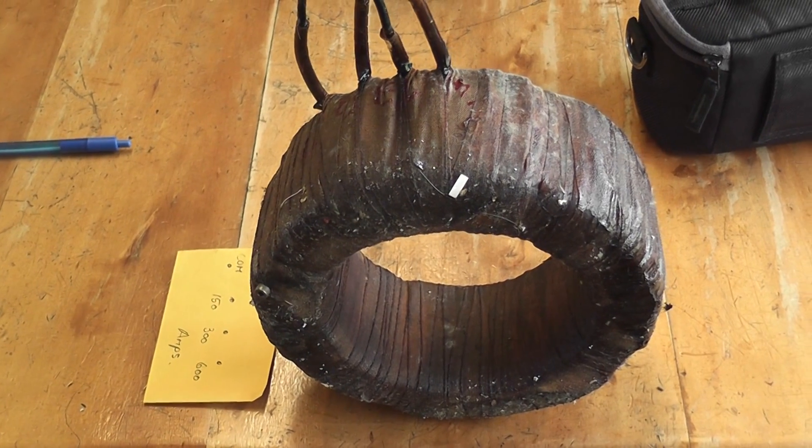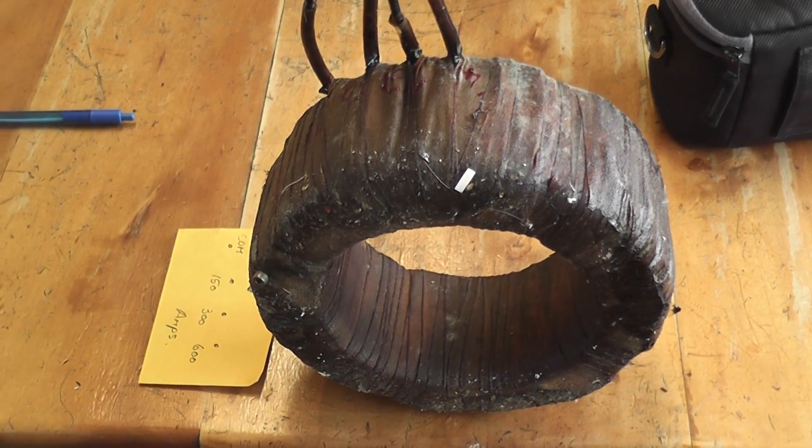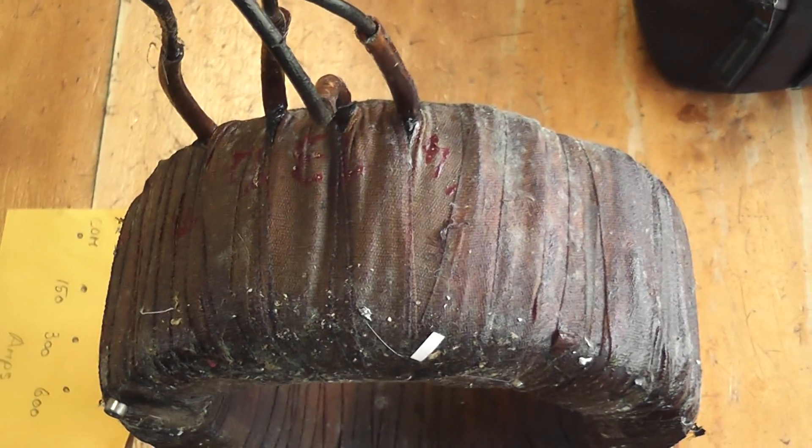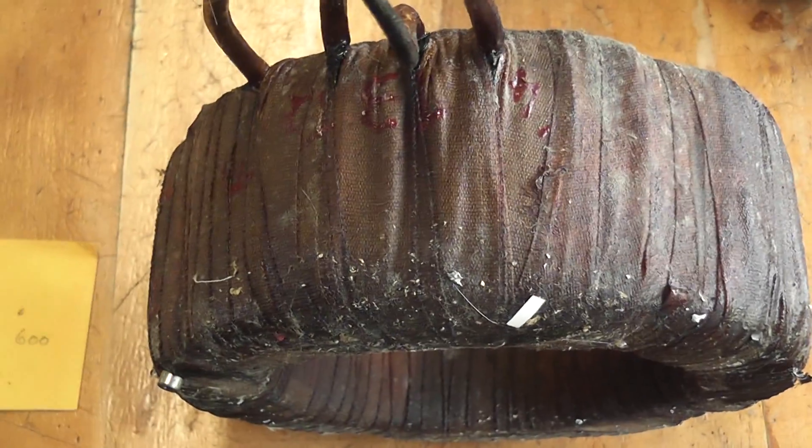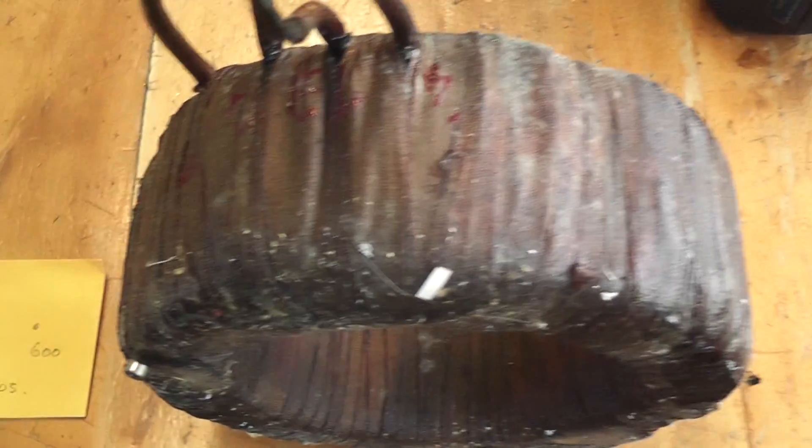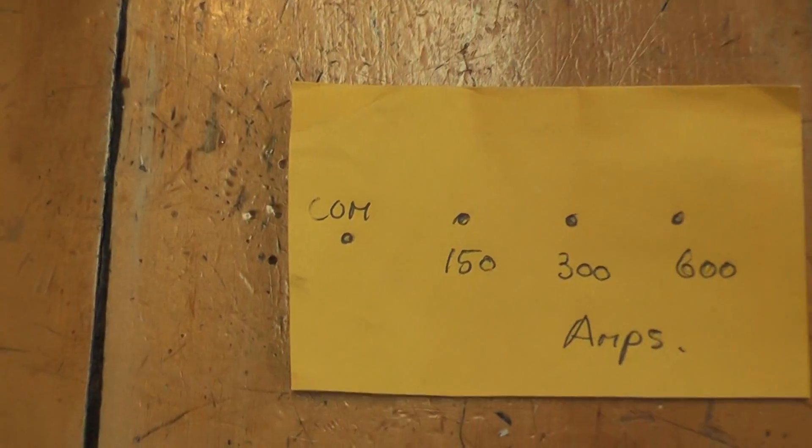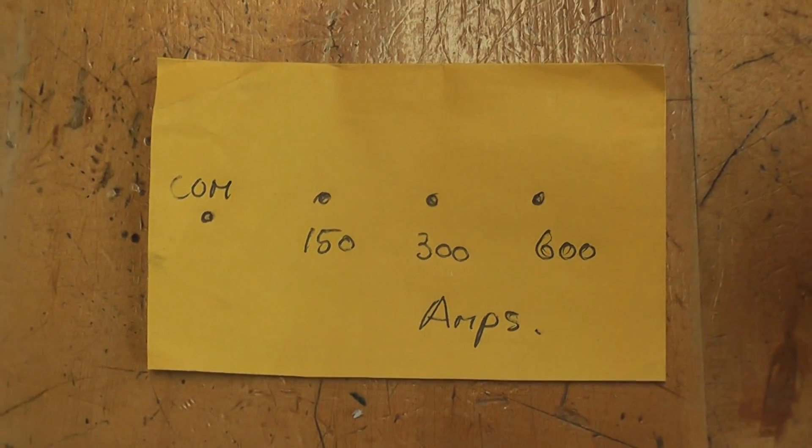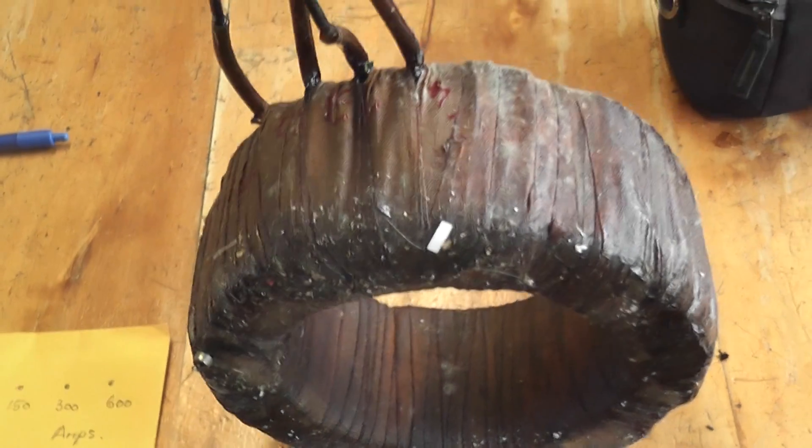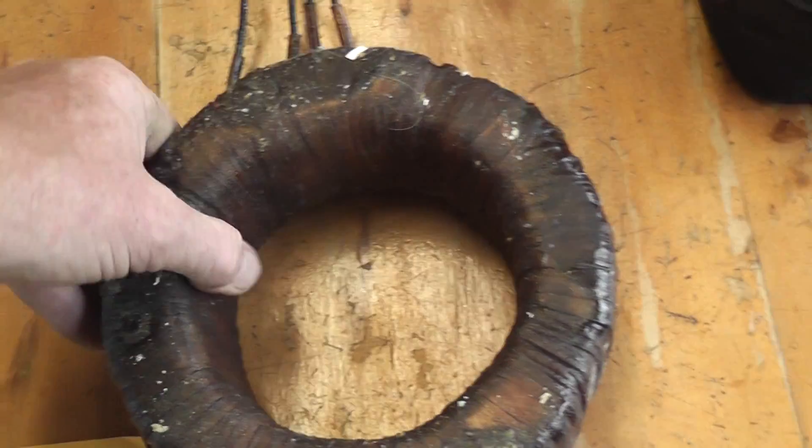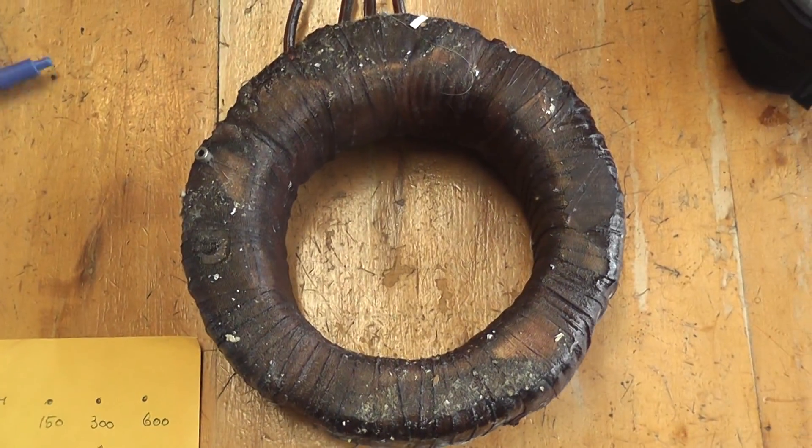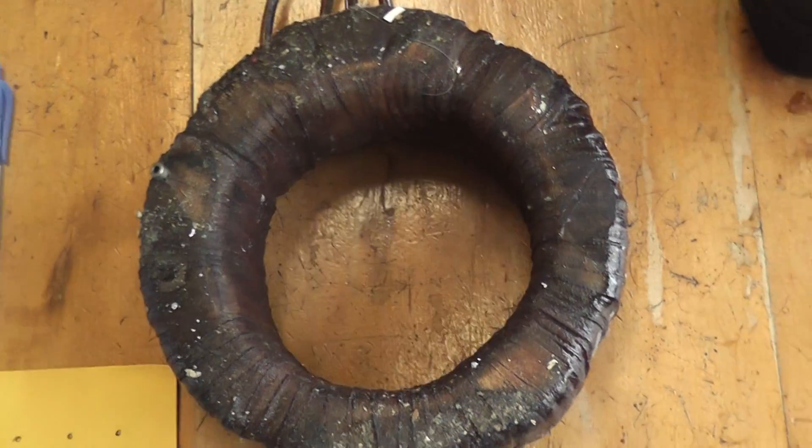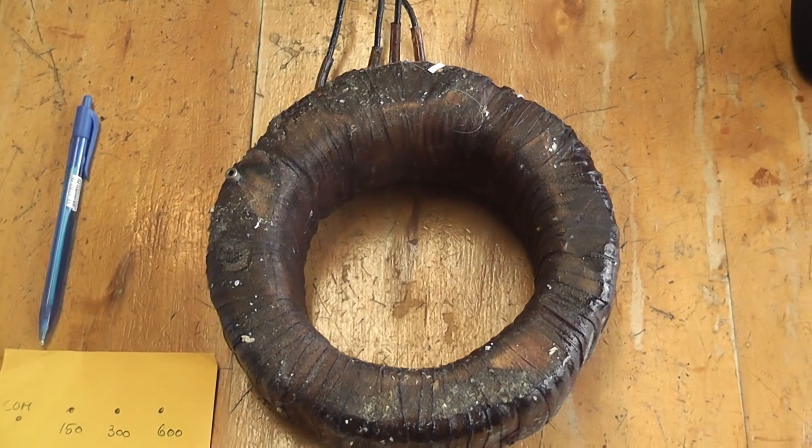Some CTs are multi-tap, this particular one is labeled 4321. Basically this one comes out of a 33,000 volt circuit breaker. It has a common terminal 150, 300 and 600 ampere. Quite a big one but it will do exactly the same. It can also be used at normal 240 volt mains voltages.